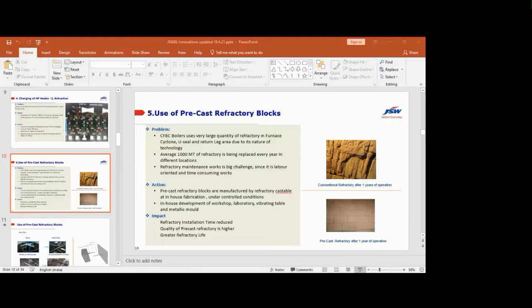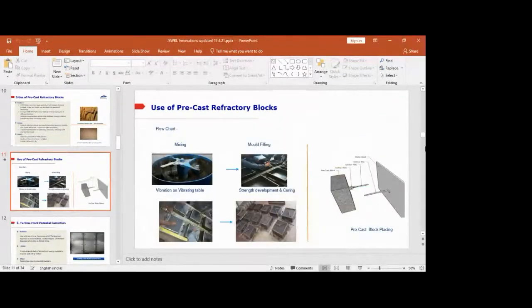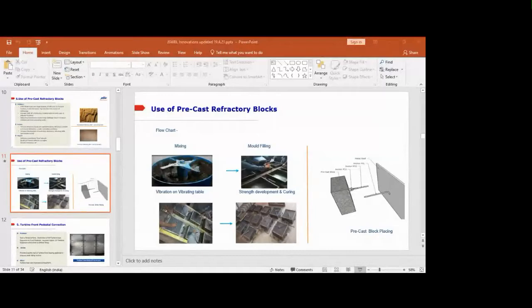For this, what we did: the flow chart for precast refractory is first mixing, then mold filling, then the vibrating table, strength development and curing. All this work is done at the workshop. When the block is ready, it is shifted to the site and the anchor is provided in the block, and one anchor is fitted at the metal plates. Both anchors are welded and the insulating material is directly filled here. The time is hugely reduced and the refractory life is very good.